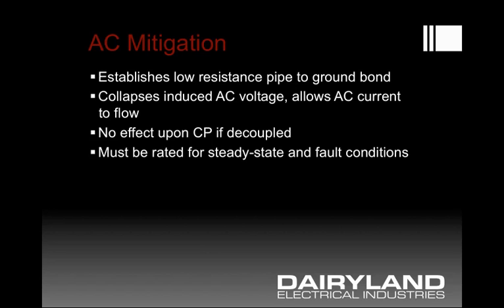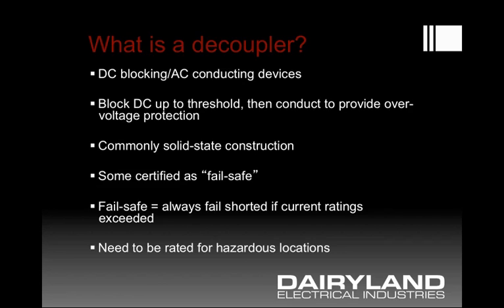A decoupler is a DC blocking device that can simultaneously conduct AC. It blocks DC up to a threshold voltage — usually several volts — and beyond that voltage, which would be considered abnormal, it turns on and conducts to provide overvoltage protection for lightning, fault current, or any other abnormal condition. These days this device is typically solid state and is generally fail-safe: if exposed to current beyond its ratings, the device will always fail as a short. This can be tested in a power lab to confirm that excessive current produces the desired result of failing shorted. It would not be desirable to fail open, as you'd have no further overvoltage protection of any kind.